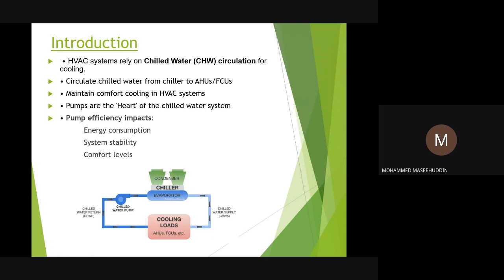Okay, guys. So this is a basic chill water circuit, a small circuit, where the chill water pump takes the warm water coming back from the building on the return side and pumps it to the chiller. Then from the chiller it goes to the building loads, which are the cooling loads like AHUs, FCUs, etc., and rolls back to the pump. So it's basically a closed circuit. All the chill water pumps in the chill water segment come under the closed circuit.